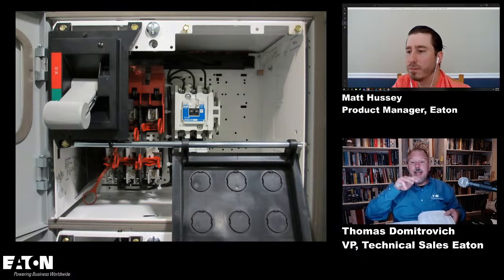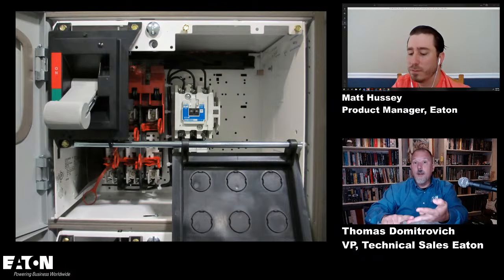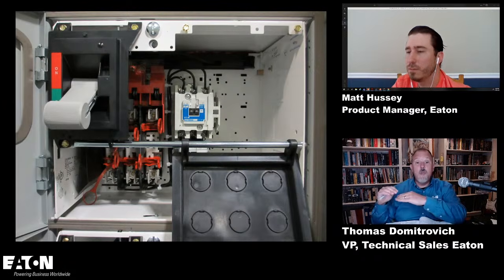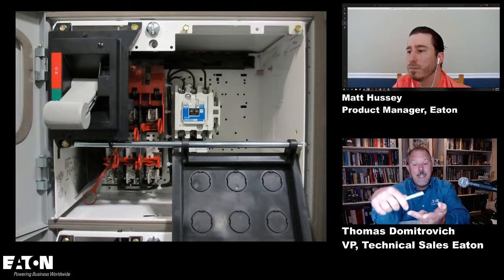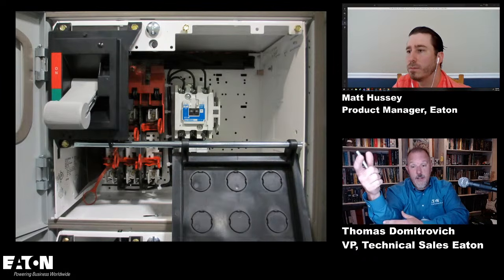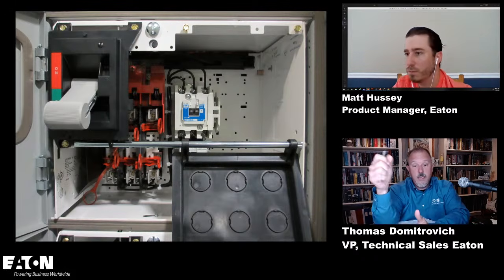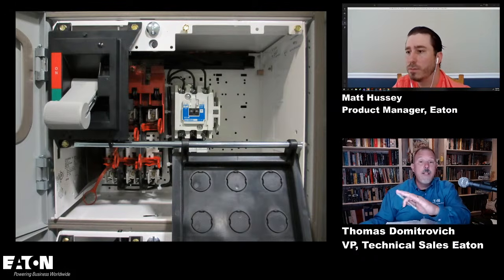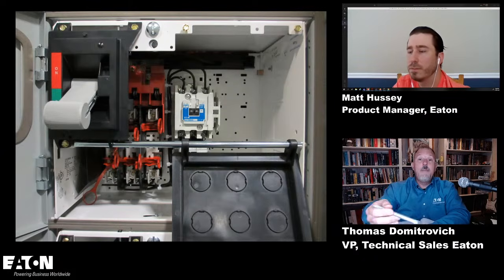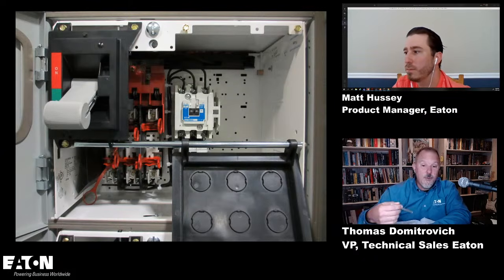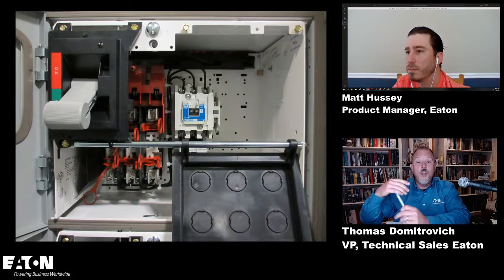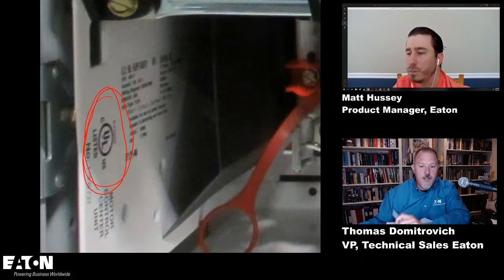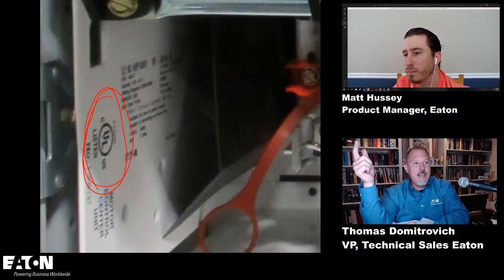But when you start looking at a lot of these things, when you consider heat rise and the requirements from a short circuit current rating perspective, there's only so much an inspector is even able to do. That's why they'll typically get an organization like UL or ETL to come out and do a field evaluation if you start modifying these enclosures. Anytime you don't do a one-for-one, or if you're going to, like Dawn said, take that component out and change that HMCP out with a standard thermomagnetic circuit breaker to feed a panelboard, you are into the area of an AHJ, in my opinion. Yep, a field evaluation. That is, if you're even going to get an inspection, right?